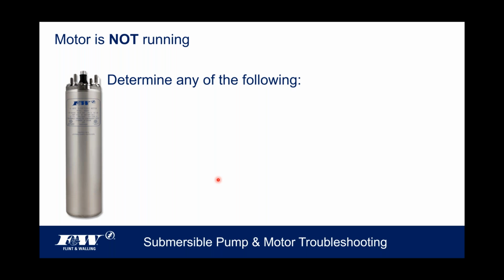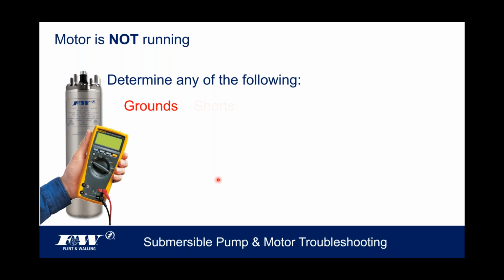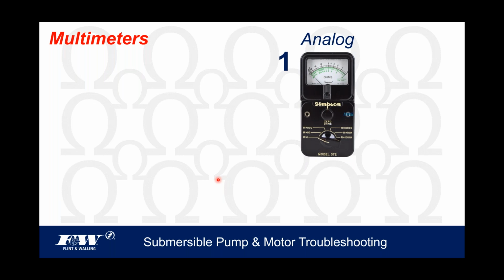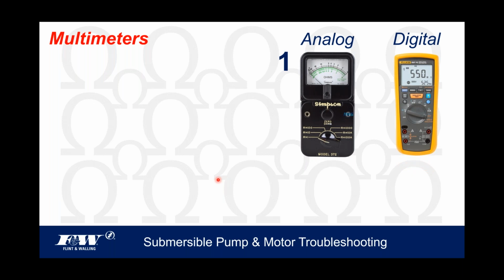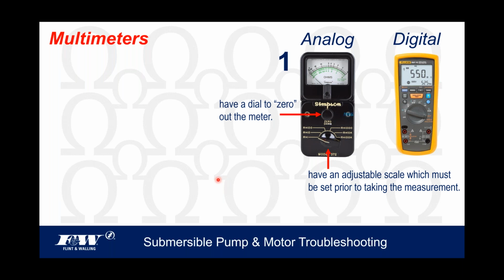So if the motor's not running, with a simple multimeter there are any number of things that we can determine, all right? We can determine if a motor is grounded, if it has shorts, if it's got open winding or mixed leads. When it comes to multimeters, there's a couple of choices out there still to this day. Analog, which is what you see on the screen there. If you do happen to use an analog meter, don't forget that you have an adjustment scale down at the bottom that you need to set prior to taking any of your measurements. And then there's also a dial up in the center of that thing so that you can calibrate it each time you use it. In other words, you're going to zero that meter out with that dial up there.